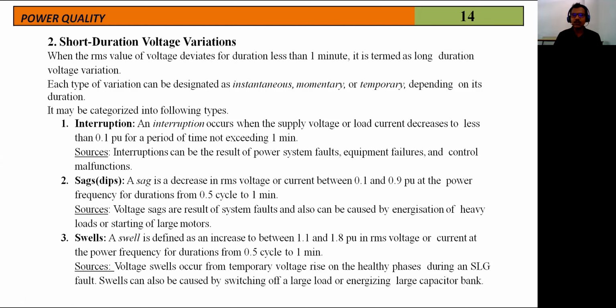So an increase in the voltage or current between 1.1 and 1.8 per unit. If the voltage or current exceeds the rated value, that is called a swell. It generally ranges from 10% to 80% increase in the voltage or current, 1.1 to 1.8. The sources: voltage swells occur from temporary voltage rise on the healthy phases during a single line to ground fault. When a single line to ground fault occurs, the voltage on the other, healthy phases will increase. That is called a swell.